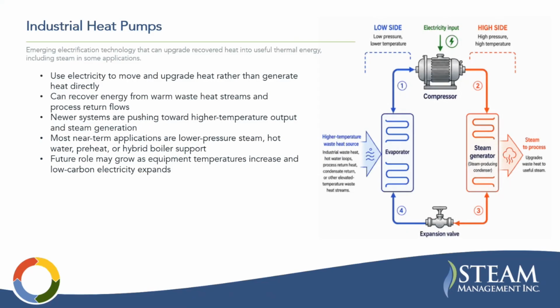One option that's kind of a buzzword lately is industrial heat pumps. So it's emerging electrification technology that can upgrade recovered heat into useful thermal energy, including steam in some applications. I would say for steam generation, a lot of the designs are still dependent on a higher temperature heat source than just ambient air. But it can recover energy from a warm waste heat stream and generate steam potentially. There's also designs where the lift is done in stages to get a higher temperature output. But if you have several loops, now you're starting to lose the efficiency.